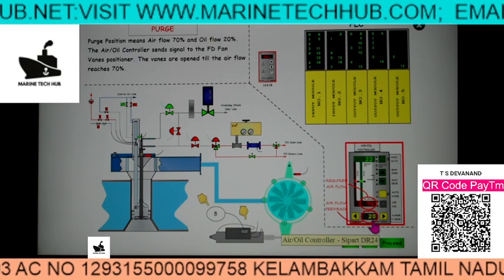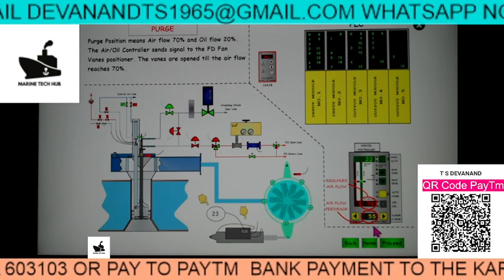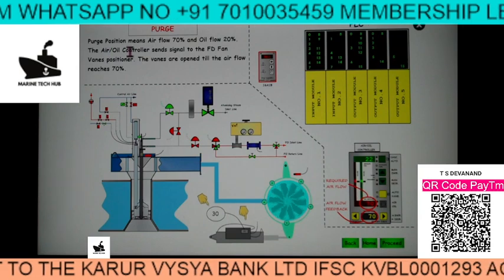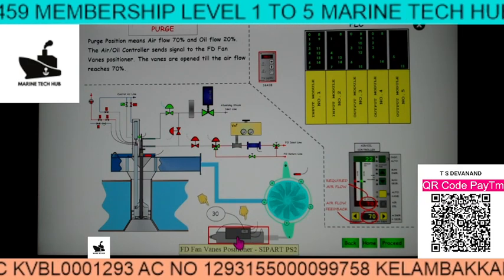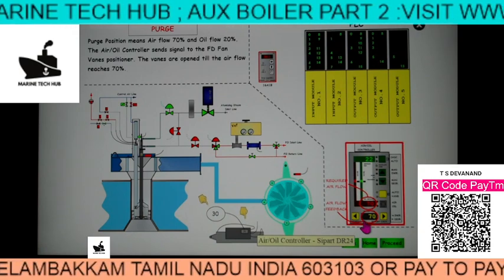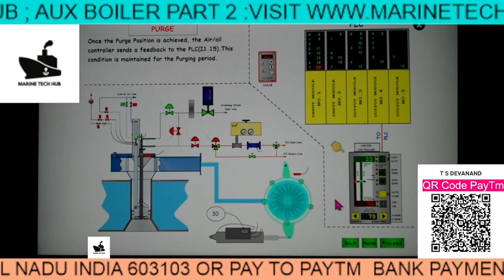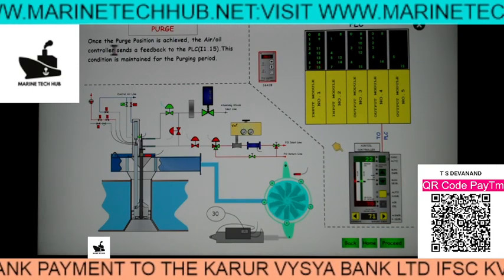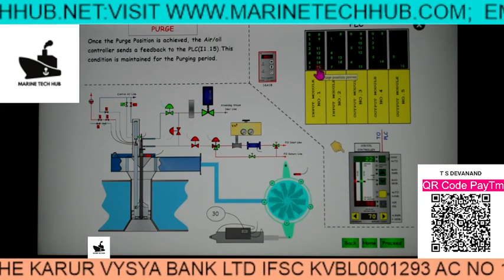Once the purging position of 70% is achieved, the air oil controller sends a signal to the PLC at I1.15 — this means 'purging positioner.' Now we need to give the ignition position. The FD fan vane is closing up and will come to 20%. Once it comes to 20%, that means we are ready to fire the pilot burner. At ignition position both air and oil are at 20% for firing. The controller signal and vane positioner are both checked to confirm the position has come to 20%.